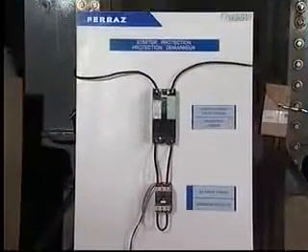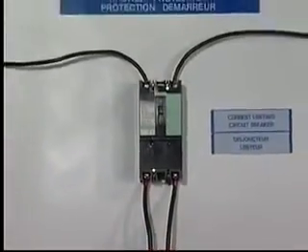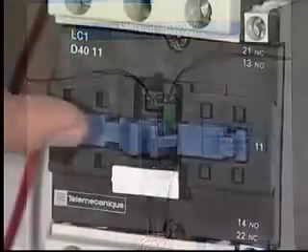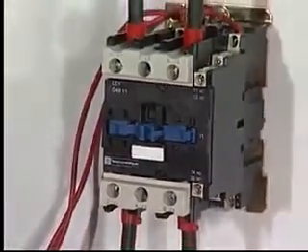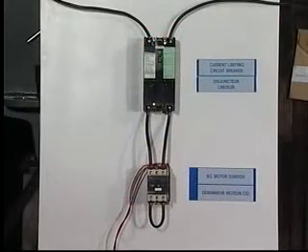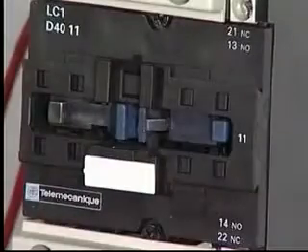The second test shows a current-limiting breaker in the hopes that the current limitation will improve the protection level rating. Identical test conditions are used. A new starter has also been installed. Once again, the contacts are fully functional before the test. Although the amount of outgassing is significantly reduced, the starter contacts again appear to be welded.